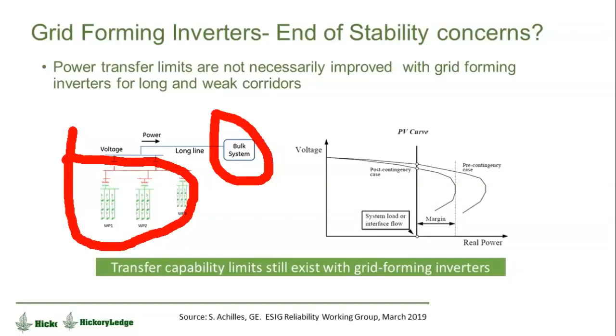So to wrap up so I can take questions: we are looking down the barrel of a transformation. We've done a spectacularly good job as an industry making grid following inverters better and better, more stable, more tolerant of weak grids, more able to respond in a beneficial fashion to grids. But it's taken us 15 years, and there is a limit—we're getting to a point of diminishing returns as the size approaches big or infinity relative to the stiffness of the grids. With inverters, we have the building blocks that allow them to look a lot like synchronous machines, but we can do better, and we haven't figured out exactly what better really needs to be. So, pounding on the table here to say, we've got homework to do.